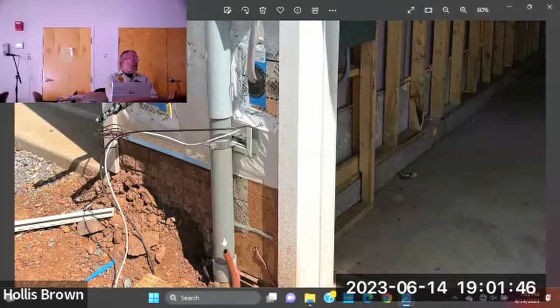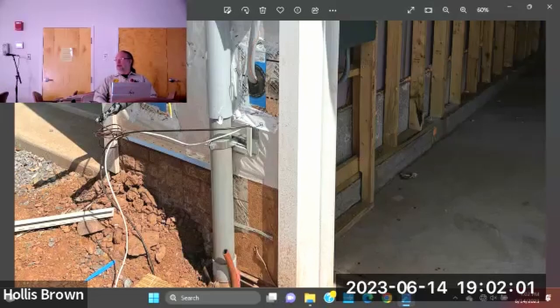And that would pull this out. This is now a separate piece of pipe with a sleeve that can move, so if it pulls, as long as there's some slack, it won't destroy the meter can and cause fires and explosions. Is that required now? If it's not there, is it up to code? Jurisdiction by jurisdiction - I think PEPCO requires it. I'm not sure about Allegheny or any of the other providers.